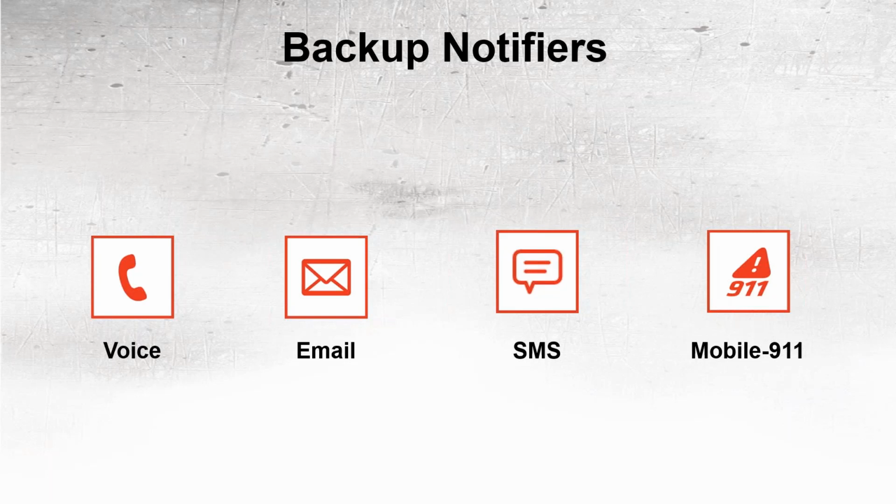So a common use case would be that when you get an alarm, you send an email as soon as the alarm occurs. Give the operators maybe 5 to 10 minutes to respond to the alarm. So in this new Win911, you can reply to email alarms and acknowledge them. So maybe after the 5 or 10 minutes, it hasn't been acknowledged. Then you can go ahead and trigger some other notification method, maybe like a phone call. If it's a phone call, if they didn't see the email, they'll most likely hear their phone ringing, for example.